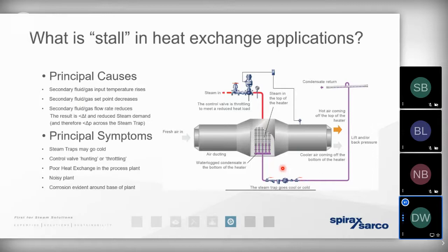So on an occasion such as this, well, the condensate will back up and start to flood the heat exchanger. And because there's less energy present in the condensate than there is in steam, we're not going to be able to get the energy into the duct or into the process. The sensors in the ductwork would send a signal to the control valve, calling for more and more energy. The control valve would open wider and wider. As the control valve opens wider, that increased steam pressure pressurizes the condensate. The condensate is driven out of the coils with quite a lot of violence, across the steam trap with quite a lot of violence. We get a huge fall in pressure, creating quite a lot of that flash steam that we've spoken about. So we get the flash steam vented away to atmosphere. We get a rapid release of energy, creating water hammer.